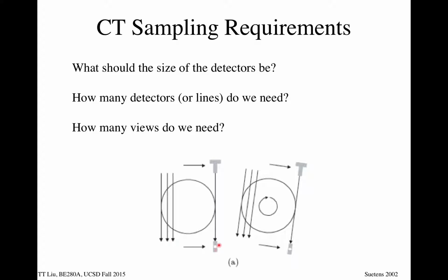So yeah, we have the width of this detector. So we make this thing 50 microns wide, so it's looking at a very narrow line through the sample. And then we also discussed, but we didn't do it in detail, the fact that unless the X-rays are coming from a point, we have a problem. Say the X-rays are coming from a very wide source. The X-rays from over here can be passing through, hitting our detector. X-rays from over here can pass through and hit our detector. So that also blurs the picture, and that's the spot size.